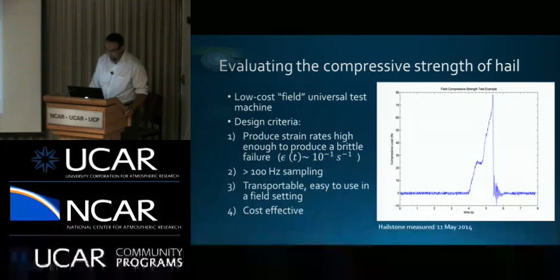The device itself is calibrated using a dead load, so we would actually put the device into an Instron, essentially press down on it with a known load, and develop that voltage versus load calibration curve.